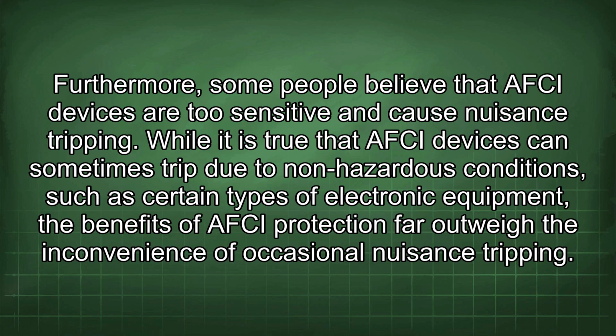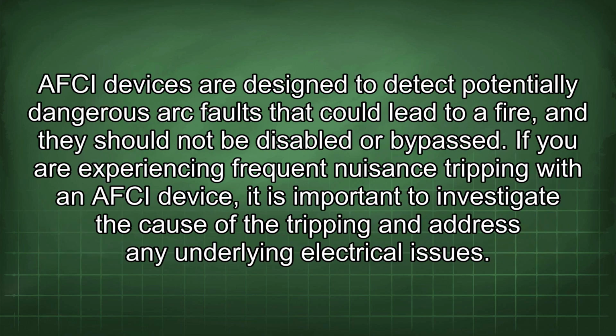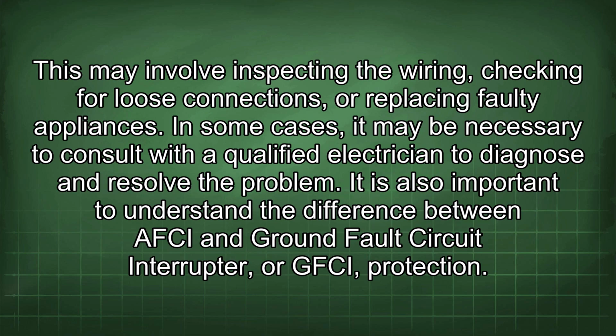While it is true that AFCI devices can sometimes trip due to non-hazardous conditions, such as certain types of electronic equipment, the benefits of AFCI protection far outweigh the inconvenience of occasional nuisance tripping. AFCI devices are designed to detect potentially dangerous arc faults that could lead to a fire, and they should not be disabled or bypassed. If you are experiencing frequent nuisance tripping with an AFCI device, it is important to investigate the cause of the tripping and address any underlying electrical issues. This may involve inspecting the wiring, checking for loose connections, or replacing faulty appliances. In some cases, it may be necessary to consult with a qualified electrician to diagnose and resolve the problem.